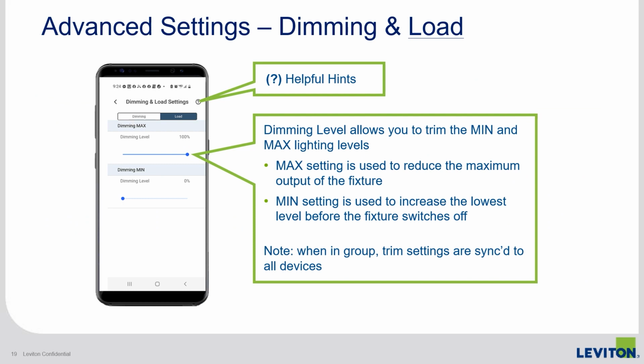To set the trim levels, go to the Load section. The dimming max level is used to reduce the maximum output of the fixture. This level becomes the new max bright output. The min setting is used to increase the lowest level before the fixture turns fully off.